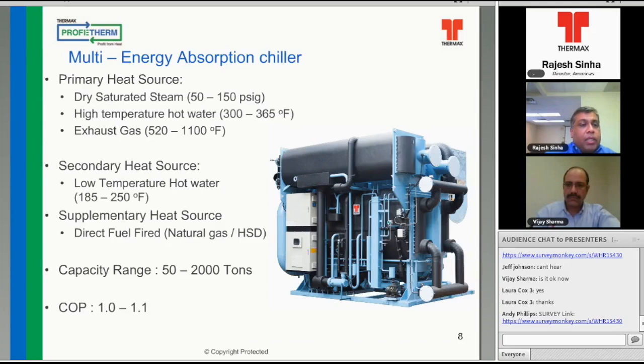Then we come to the multi-energy absorbers. The multi-energy absorbers can simultaneously handle several different sources of heat as could be available at a particular premise, and this could simultaneously run on any or all the combinations of these heat sources. Typically, there is a primary heat source which runs the two-stage cycle, which could be dry saturated steam, high temperature hot water, or exhaust gases.